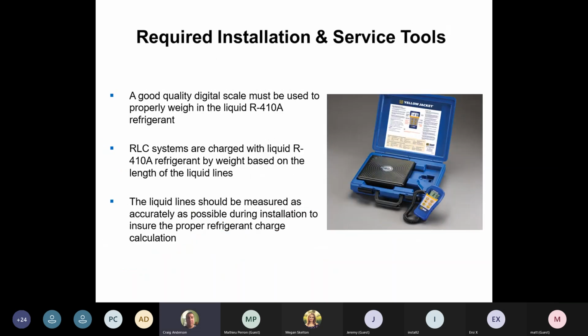Scale. If you don't have a scale in your truck, you're not installing an air conditioner properly. Every truck should have a scale, whether you're a service guy or you're an install guy. If you're working on an air conditioner, you want to weigh in your gas. We're dealing with variable speed compressors. We're dealing with two-stage compressors. We have no idea what stage that variable speed compressor is in. So really looking at your gauges is not telling you what's going on. All it's telling you is you have gas in the system and your compressor is running. If you don't know what stage it is, you really have no idea what your pressure reading should be at that point.